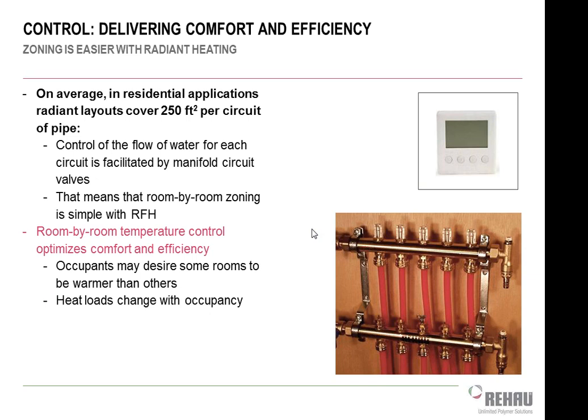On average, we're typically going to have heating circuits limited to about 250, maybe 300 feet per circuit of pipe. The idea with having smaller circuits is that I don't need as much pumping horsepower to push water through these circuits. So we tend to have the circuits be smaller, and we tend to group them by zone, obviously, so we can have individual thermostatic control over each individual zone. So if I've got 250 feet per circuit, that's going to cover a certain floor area. That's going to be a bedroom or two or something like that. So every room can end up having its own thermostat for not too much additional cost. It's basically the cost of an extra thermostat and an extra valve, versus on an air side system, I'm going to have some kind of logic control panel, dampers, actuators, and then obviously all the sensors as well. It's pretty easy to zone on a radiant side system, especially if I think about it in advance when I'm laying the tubing out.